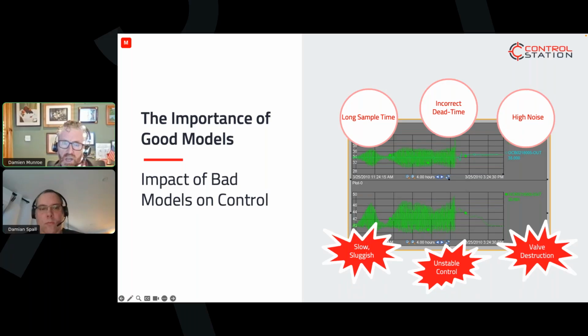It's trying to understand what's not right here, what's not in control. Is it a data problem? Is it a tuning problem? Is it a mechanical problem? But using that data to make those decisions, to make those long sample times. If you're not collecting data at the correct frequency, it's going to cause you to not get a true picture of it. You're going to sample and miss some of the color, I suppose, in the information. Incorrect dead time. Dead time is the killer of good control. If you have a wrong or particularly a long dead time, you have to wait for that dead time. Dead time actually has an important ratio to your time constant.